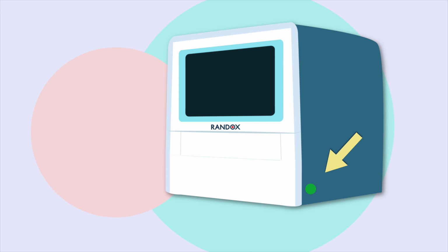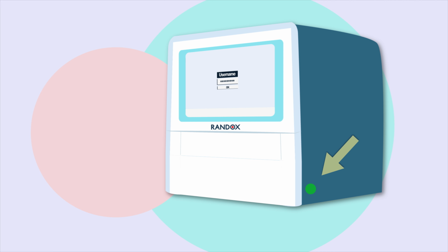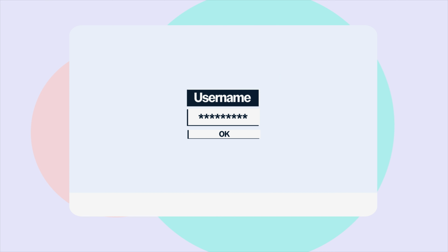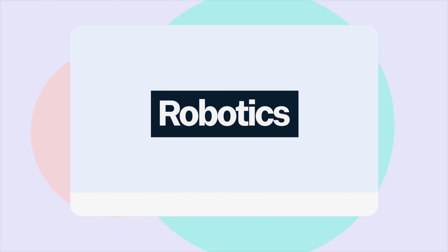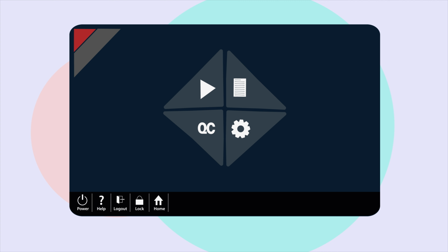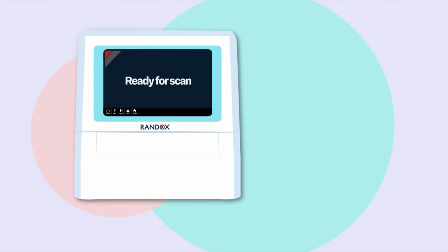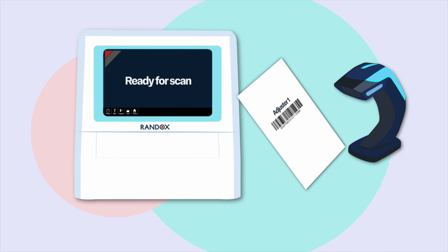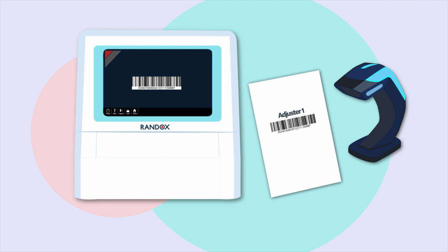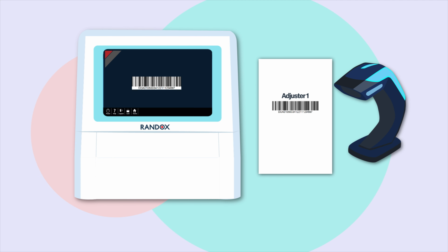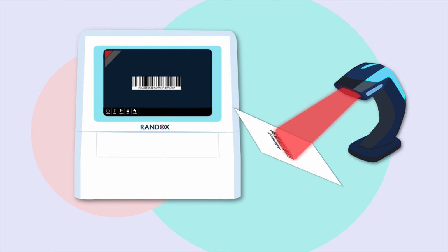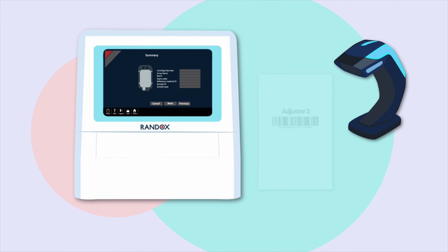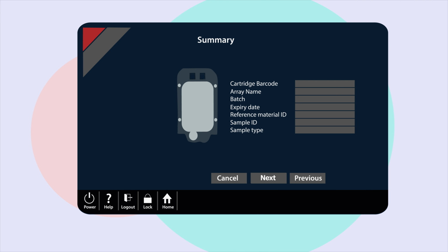First, you will need to prepare the device. Switch on the device. Log into the account you created with the Randox engineer. Select Robotics, which will bring you to the home screen. Press play to run test scan. A prompt will appear to scan a barcode. The Adjuster 1 barcode from the barcode sheet in the InflammaSTAT kit will now become the barcode for the adjusters. The system will then prompt to scan the Adjuster 2 barcode. A summary screen will then appear.